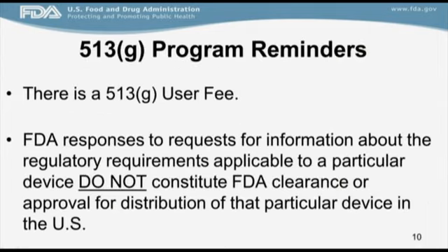There are a few caveats to the 513G program that I'd like to provide you. There is a 513G user fee, so please keep that in mind when you are preparing to submit the 513G. FDA responses to 513Gs do not constitute FDA clearance or approval. So if you submit your 513G and the FDA responds with the appropriate regulatory pathway, you still must comply with that pathway, such as the submission of a 510K or the submission of a pre-market approval application.